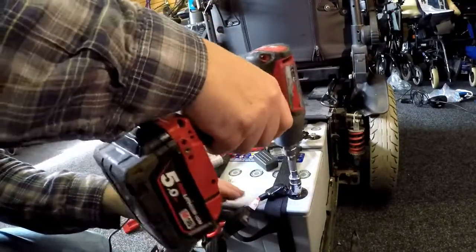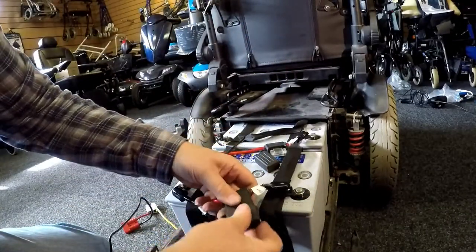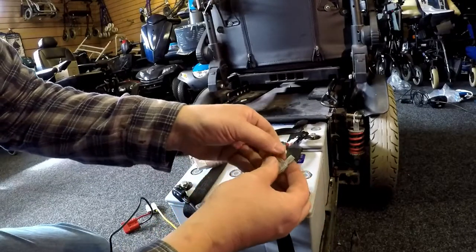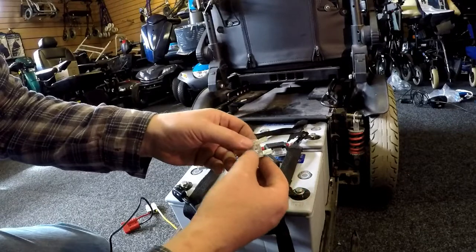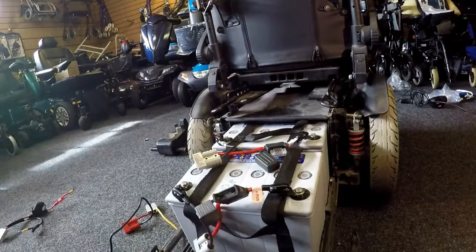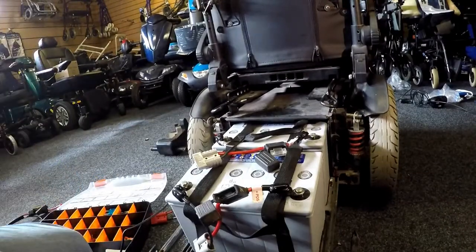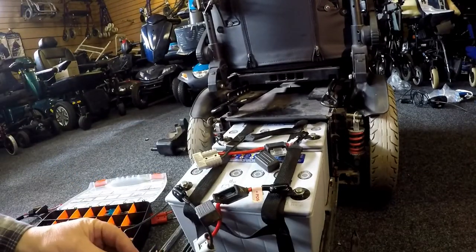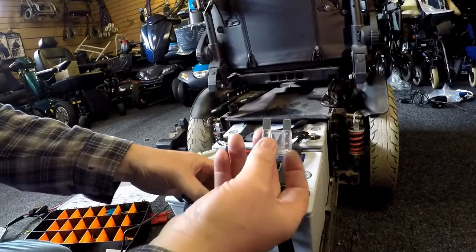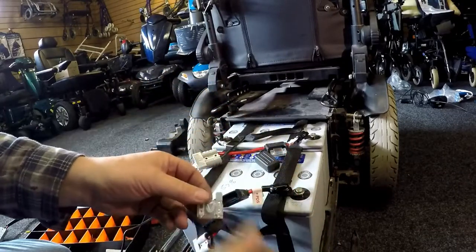Just a simple fuse, in the mould in here, that nobody can see — no voltage was coming through it. All we can try and do is clean it up. I've got my fuses — let's see what this one is. An 80 amp fuse. 80 amp — very nice and clean. That's how it's supposed to be. You can see the difference straight away. Let's pop this in here.